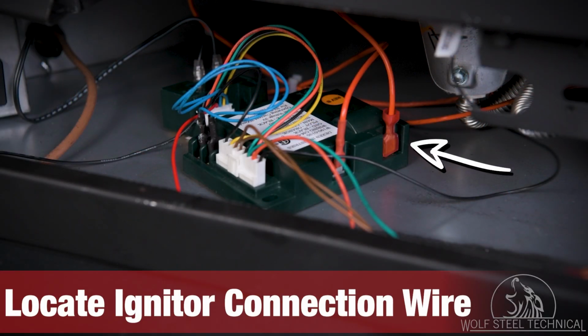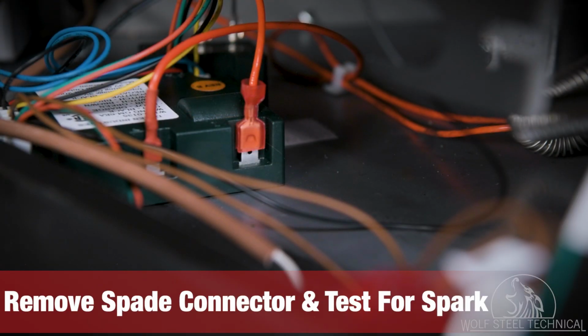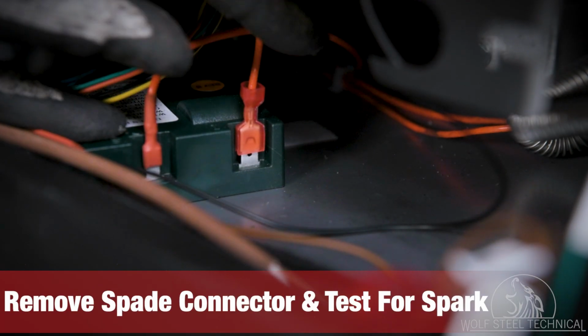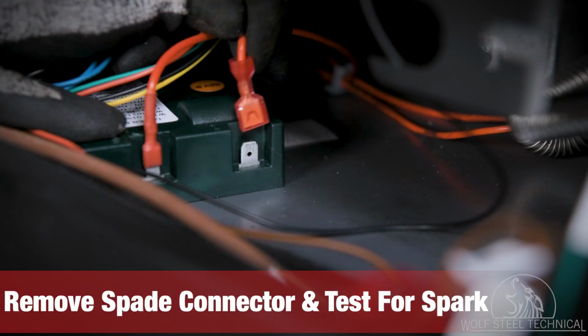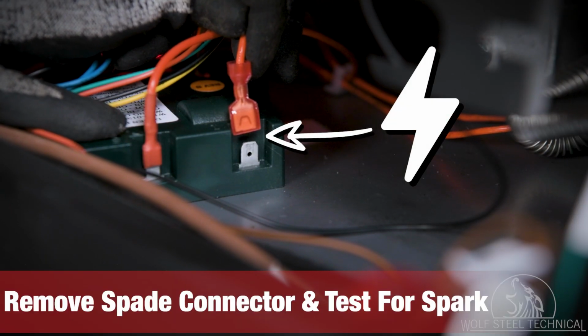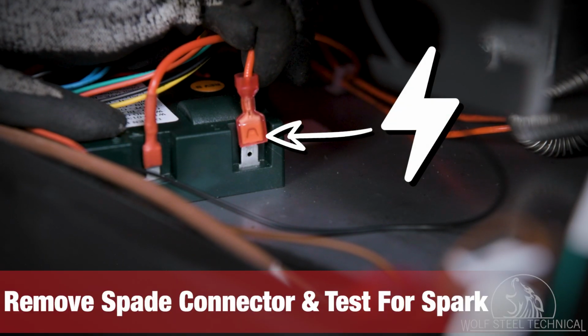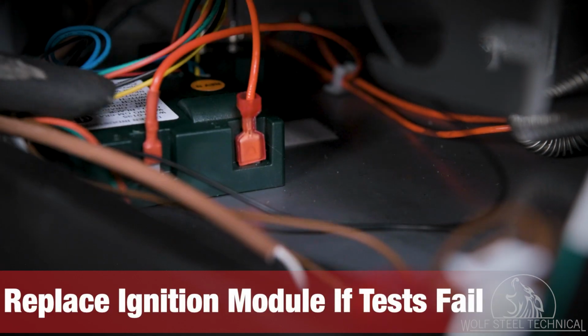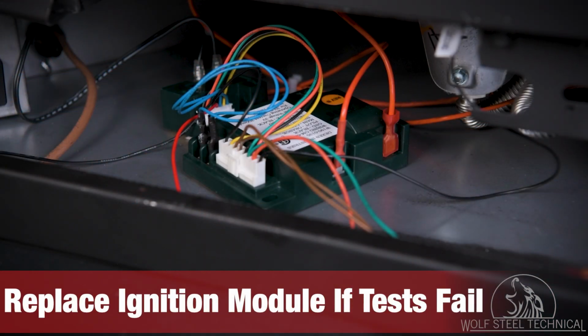Next, locate the igniter connection wire around the rear of the ignition module. This will be marked with an I. Remove the spade connector from the module and hold it about 1/8 of an inch above the pin while turning the fireplace on. You should notice a small spark arcing between the spade connector and the pin. If this or the jumper wire test fail to yield a spark, the ignition module will need to be replaced.